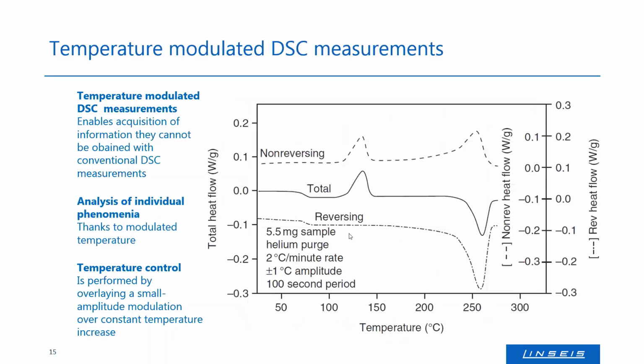But there's some more information we could get through the temperature modulation. So this is the reversing and non-reversing part of our measurement. Here in the middle of this diagram, you can see the total heat flow of, for example, PET. I think it's PET here. So we can see the glass transition at around 80 degrees, the recrystallization at around 130 till 150, and the melting at around 250 degrees. And now we can split this signal into the reversing heat flow at the bottom and the non-reversing heat flow at the top of this diagram.